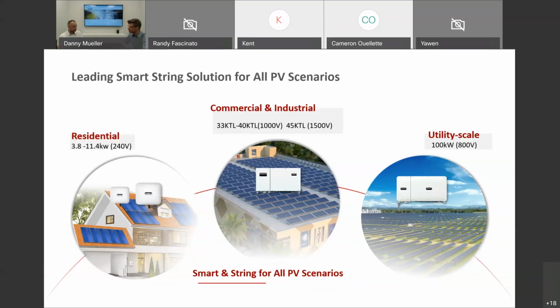And then the unit that we will be talking about today extensively is the 45 KTL, which is a 50 kilowatt, 1500 volt DC, 600 volt AC inverter. And that's really the workhorse as far as we're concerned. That's where most of the megawatts in Canada have been sold with.